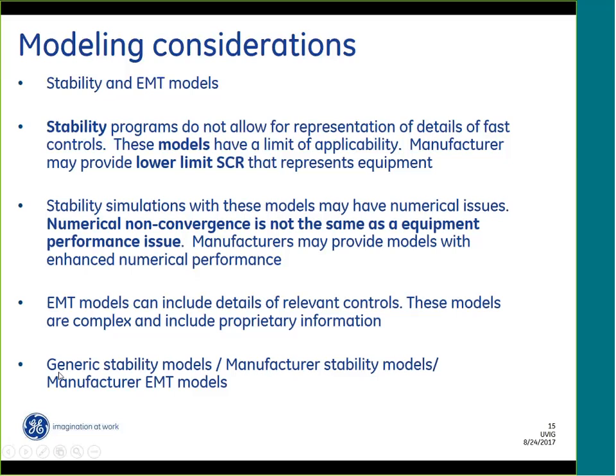So generally speaking, summarizing the modeling part, we see the industry now is basically using generic stability models. There are also manufacturer stability models that are more or less used in different systems, and then there are manufacturer EMT models. There is a trend to use generic stability models, and when there are issues, sometimes there are suggestions to jump to manufacturer EMT models. That is a possibility. We think that manufacturer stability models can be a good complement to generic stability models in many cases.